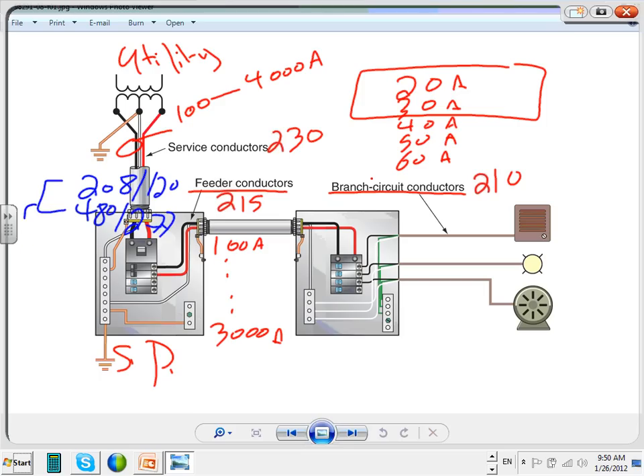Between these two voltages, you covered 90% of your commercial industrial building, and the whole system goes through. So if you get the 480, 277, you typically have to provide your own transformer. Yep, and that's what we're going to do in the next project, guys. We're going to take a 480, 277 and provide our own transformer.